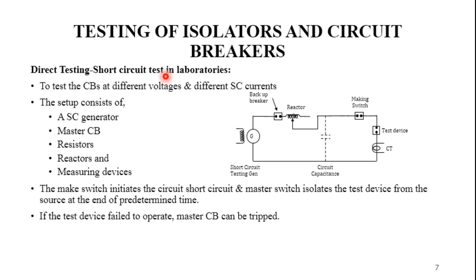The second method is direct testing of short circuit tests in the laboratory. In order to test circuit breakers at different voltages and different short circuit currents, a short circuit laboratory is used. The arrangement consists of a short circuit generator in association with a master circuit breaker, a backup circuit breaker, resistors, reactors, and measuring devices.